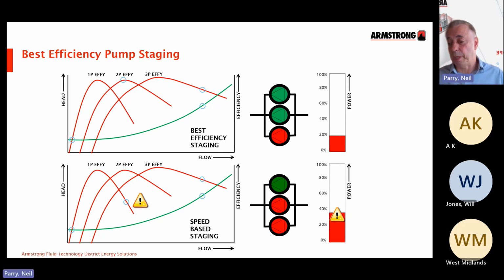That's compounded as you bring in more pumps. You get more pumps running at a poorer efficiency rate. The pump itself, our pumps from Armstrong, they have that mapped into that efficiency point, mapped into the intelligence. So what they will do is run to their best efficiency point, and then they'll hold at that point and bring on the second pump and let it come up its efficiency curve, and then hold at that pump's best efficiency point, and then bring the third pump on.